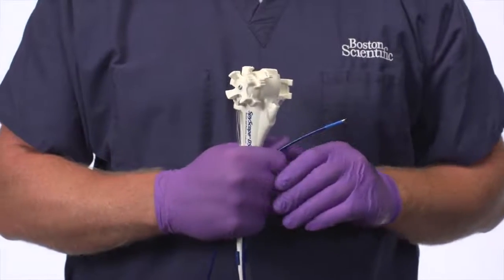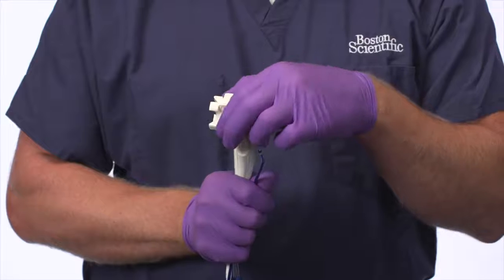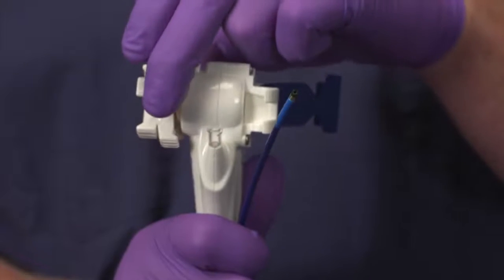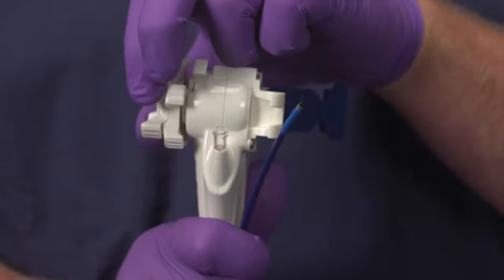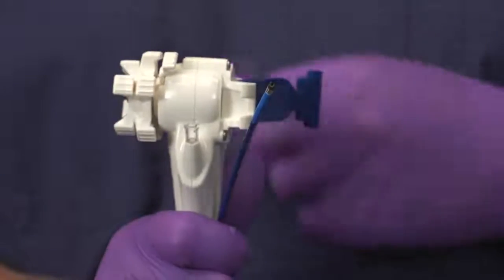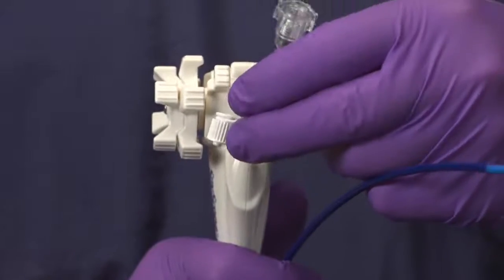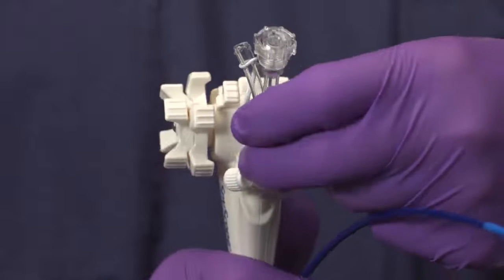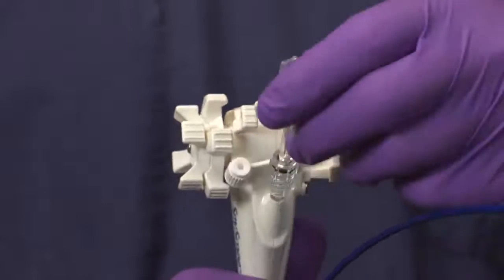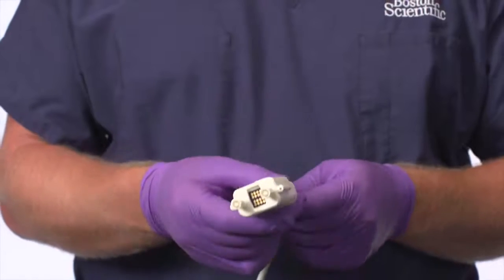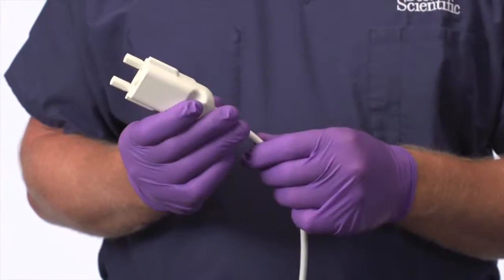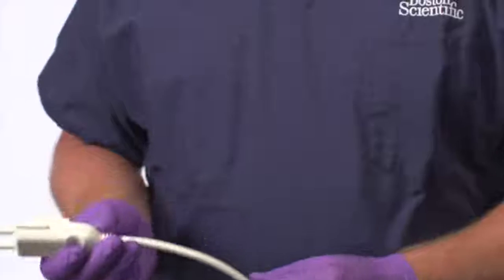Rotate the articulation knobs located on the SpyScope DS catheter handle and visually confirm articulation of the articulating section while knobs are rotated. Attach the Y-port adapter and confirm that Tuohy-Borst seal is open. Visually examine the catheter cable for kinks or damage. Visually inspect the cable connector for damage.